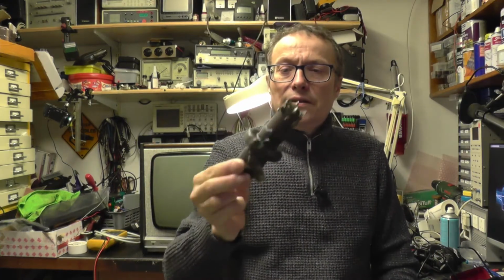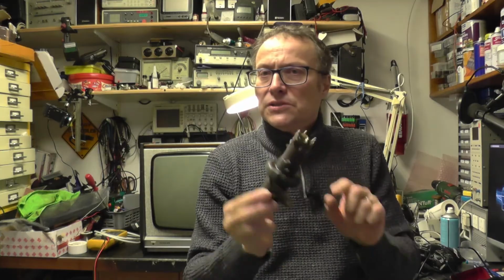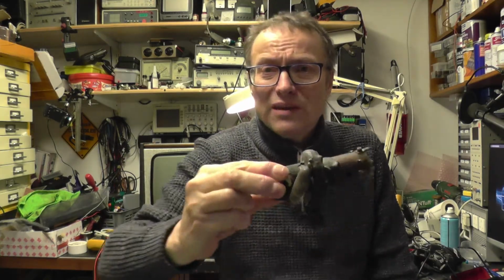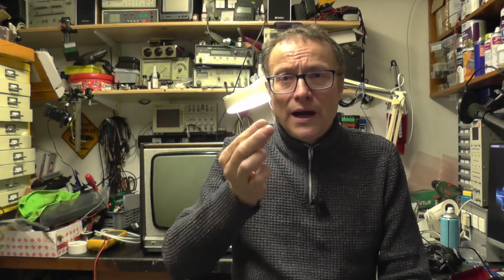But what happens is the pitch becomes slightly hygroscopic. If you look at that one closely, it's all cracked and horrible. The pitch becomes hygroscopic, lets moisture into the winding - there's a few thousand volts there. The insulation breaks down, you get a shorted turn, and that creates a load on the transformer.